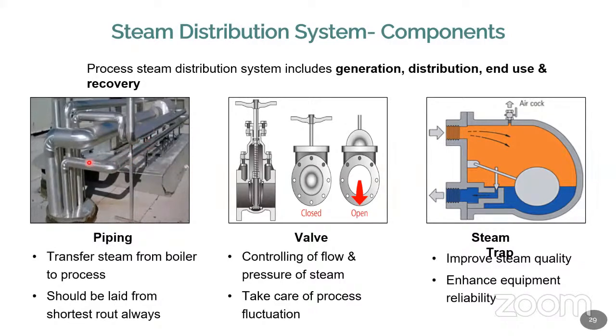Okay. Now the steam will be measured in terms of its dryness. The dryness factor indicates how much moisture content is available in the steam. So if it is 85% or 90% or 95% or 65%, that means when the steam is 85%, 15% moisture content is available. So you should have dry steam, not wet steam, in the process. So the wetness should be properly taken out. It is not avoidable, but it can be minimized.